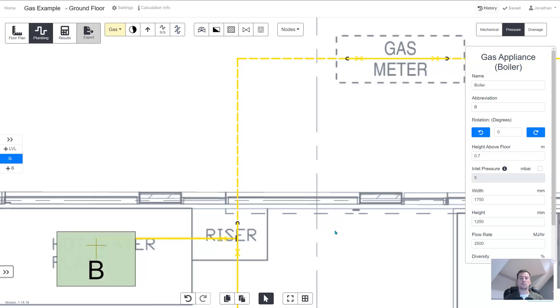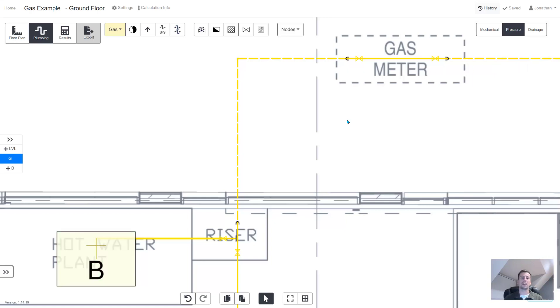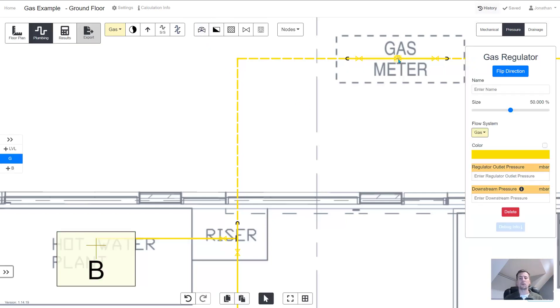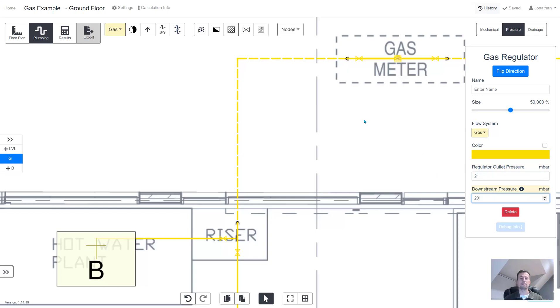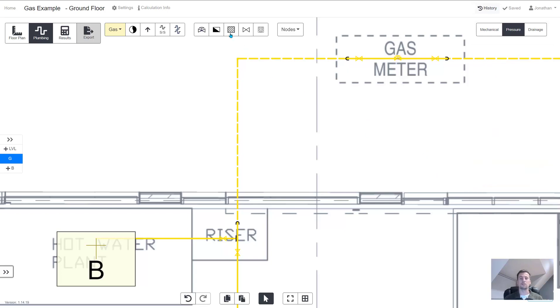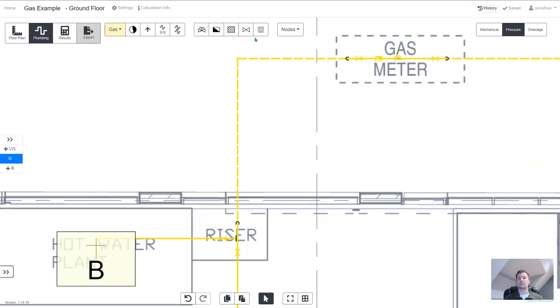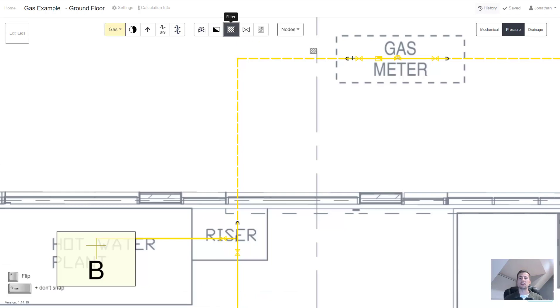Earlier we saw that we didn't change the inlet pressure and that's because we can now set it at the gas regulator. In the properties here we can choose the outlet pressure such as 21 millibar and then we can choose what pressure we want at all the appliances downstream, we choose 20 millibar, and we can go around adding meters and things to the design.